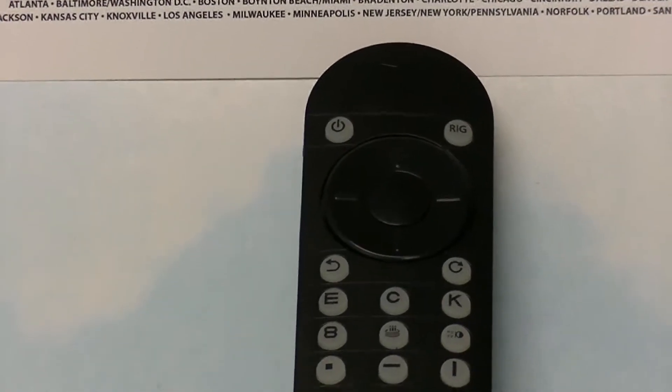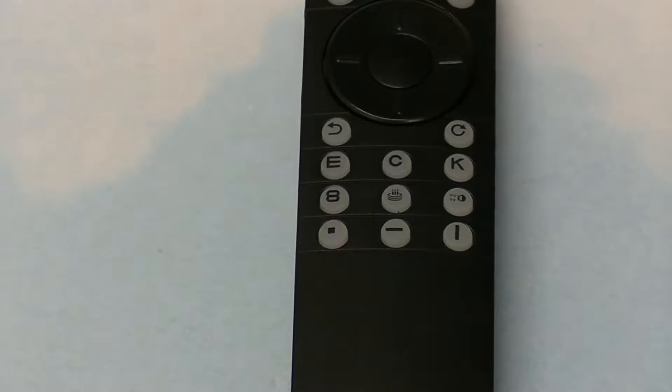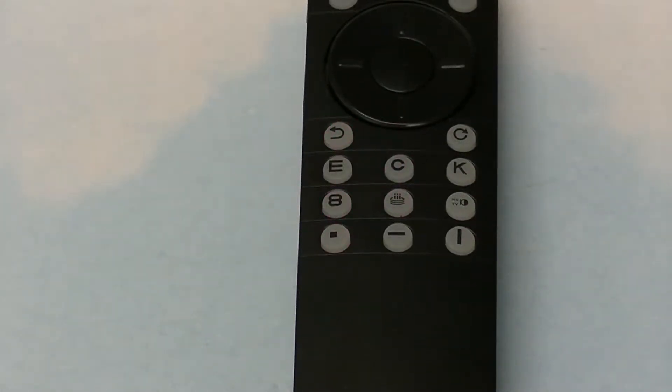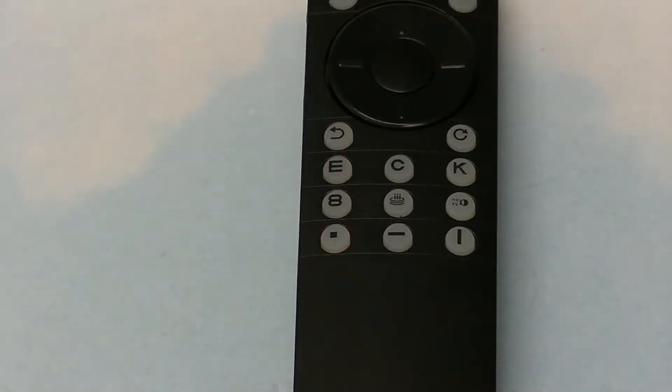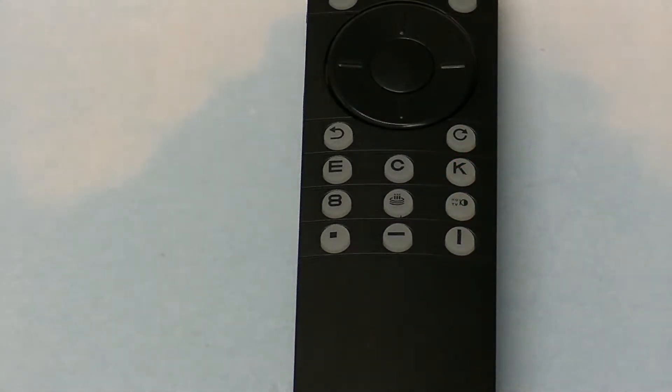Now the other buttons that are down here: the E for E-game for Snellen gives you all E's on the screen. The next one down — number — will show you numbers on the screen. That one there is the C chart, the Landolt C chart. And this one over here is the K, which means regular alphabet chart — that's the one you're going to use the most.